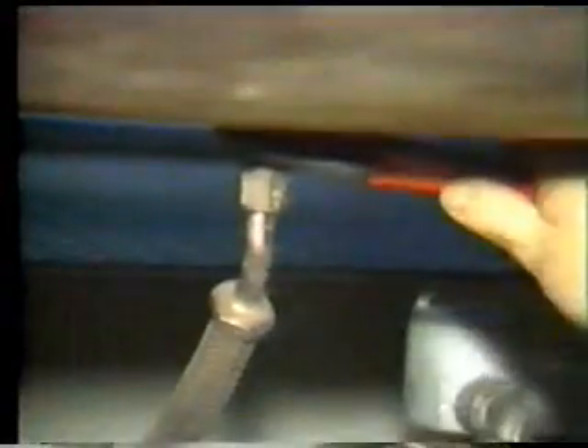The last check you will perform is on the number 4 bearing seal. This can be done by removing the drain line from the exhaust collector. When the line has been removed, check the fitting for oil leakage. Reinstall the exhaust collector drain line. If you note oil passage during the inspection, contact your solar field service representative or service manager.